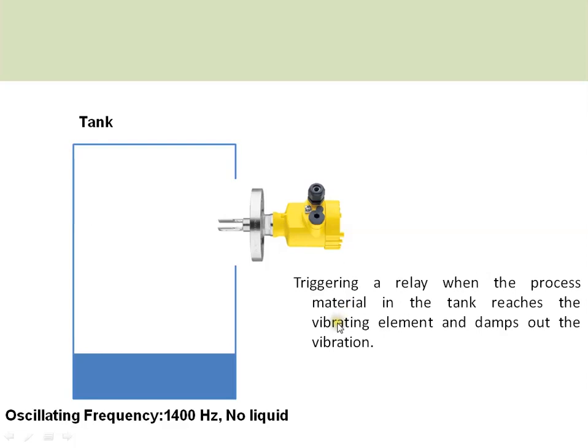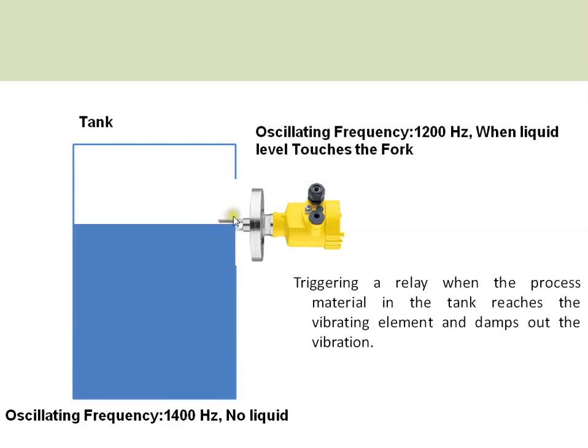As a typical example, this level switch oscillates at a frequency of 1400 Hz in air. Whenever liquid comes into contact with the tuning fork, the frequency of vibration decreases — for example, down to 1200 Hz — depending upon the density of the medium. This decrease in frequency is monitored by the electronic circuit, which then gives a signal to the output.